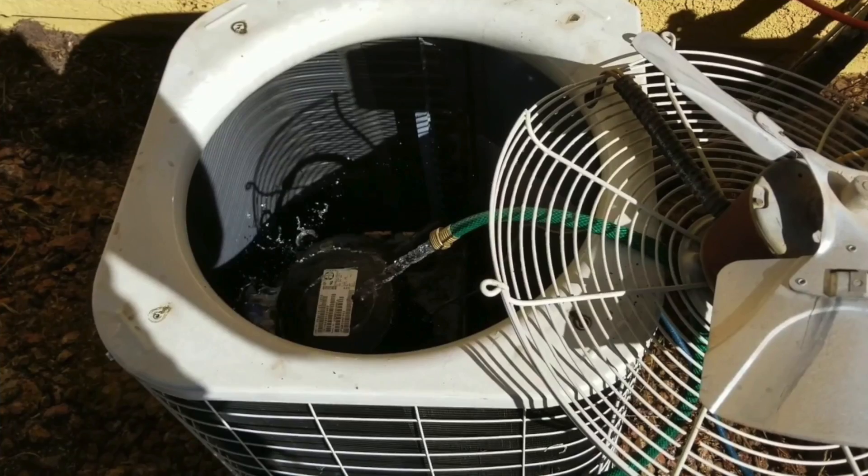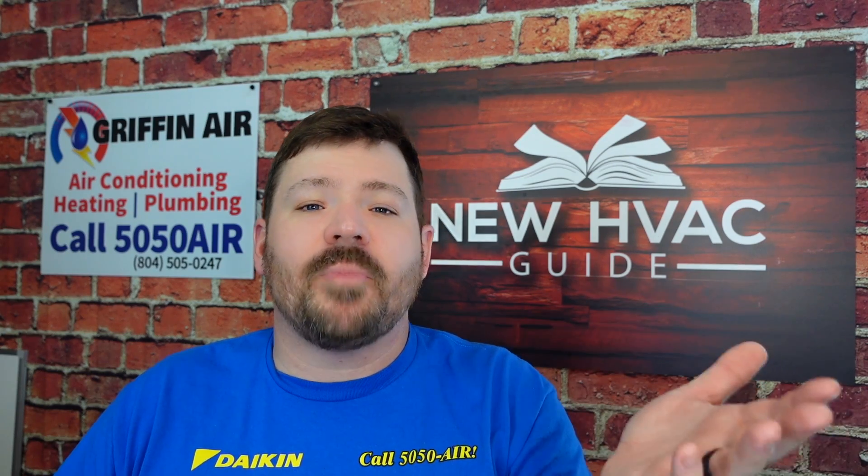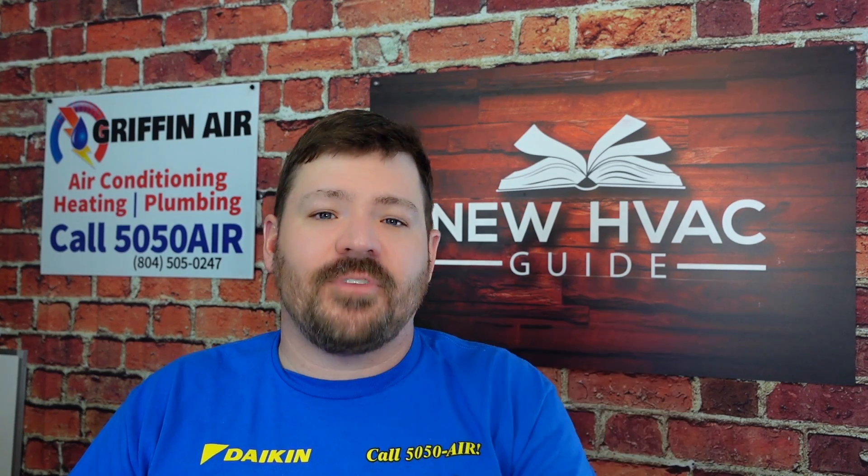I don't like to guess — I don't ever want someone to come behind me and say he was wrong. Years ago I was working at a company and one of our employees said a compressor had failed. I checked on it and found out the reason the compressor wasn't working was because it was locked out on the thermal overload — the compressor was fine. It ended up being a bad hard start. A hard start is a few hundred dollars to get the customer back up and rolling; a compressor was going to be over a thousand dollars. Had that technician taken a moment to make sure the compressor had actually failed instead of saying it's not coming on so it must be bad, he would have addressed the real problem.